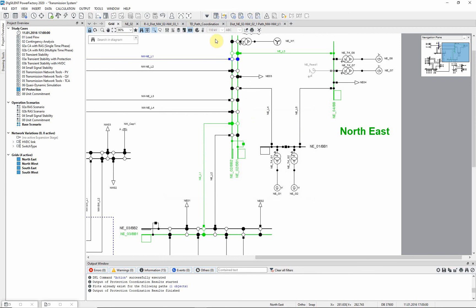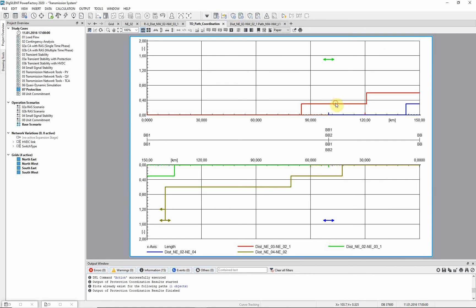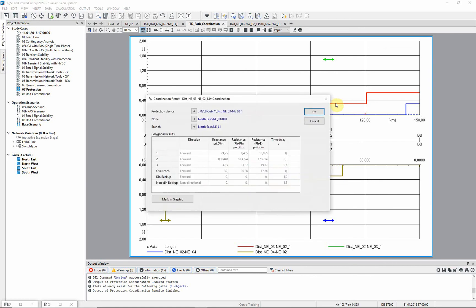The time distance diagram shows the coordination results. Every line is protected by a zone 1 to 85% of their length and the second and third zones are selective. By double clicking on a zone you see the results belonging to the associated relay.